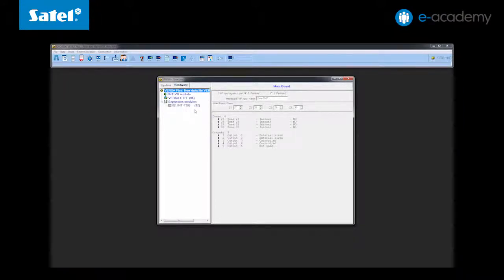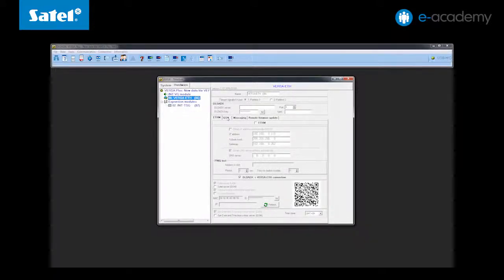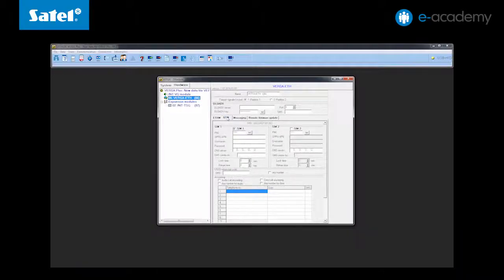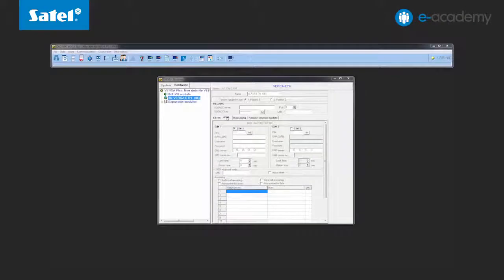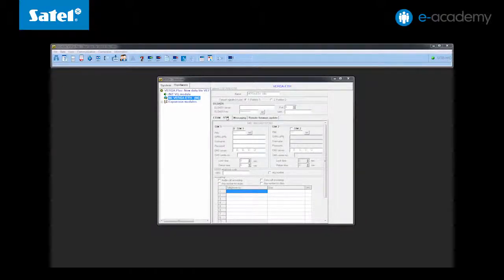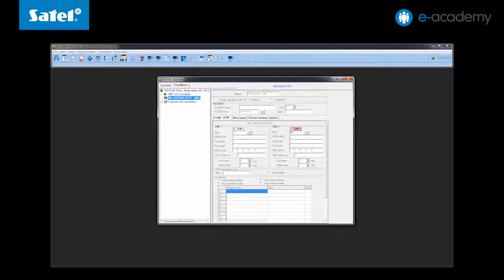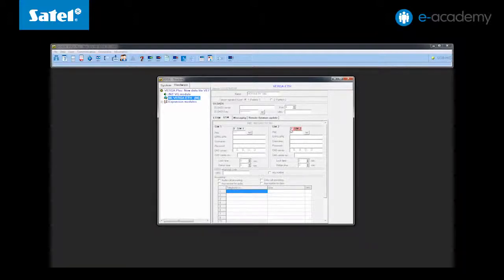In the structure slash hardware tab select the Versa ETH module and go to the GSM tab. Very important before inserting the SIM cards into the SIM card holders you have to enter at least the pin codes otherwise the card may be blocked. First you must determine whether you want to use only one card or two. To do so select the appropriate options. We will use two SIM cards. Please note that the second SIM card can be treated as a spare one.